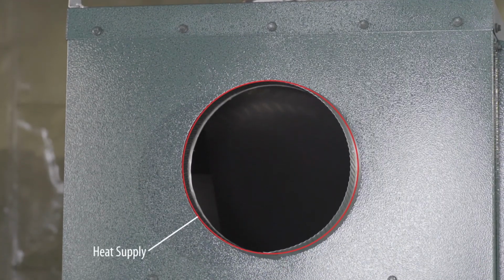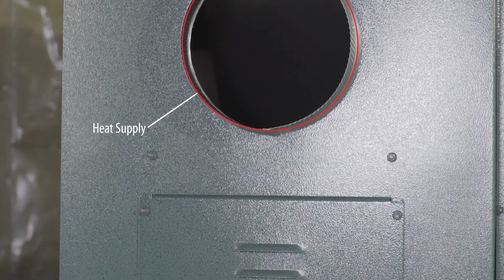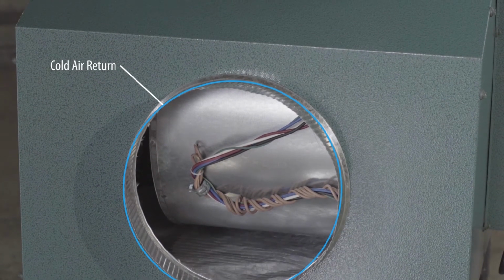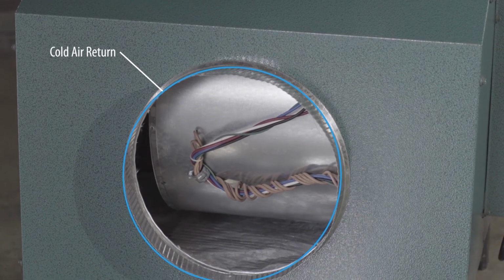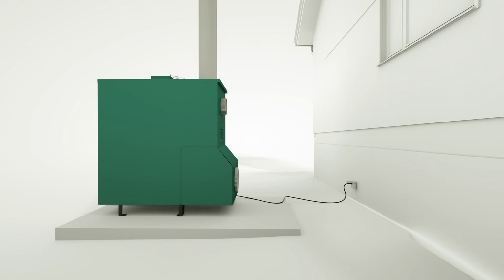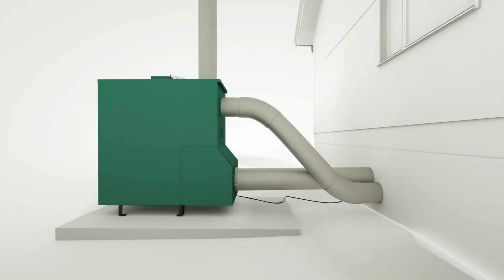The 10-inch starter collar must be connected to the heat supply vent. Then, connect the 12-inch starter collar to the cold air return on the back of the blower housing. The cold air return and hot air supply outlets from the furnace are round, so they can be used with standard galvanized ducting found at most hardware stores.